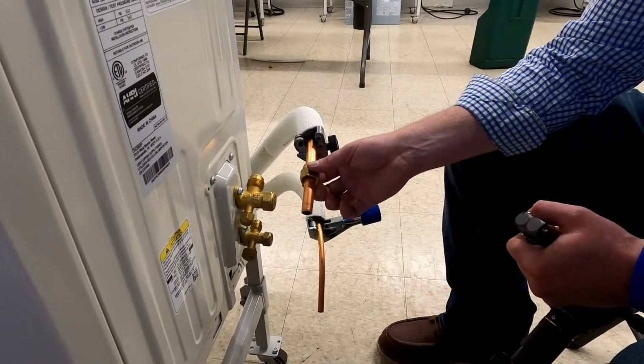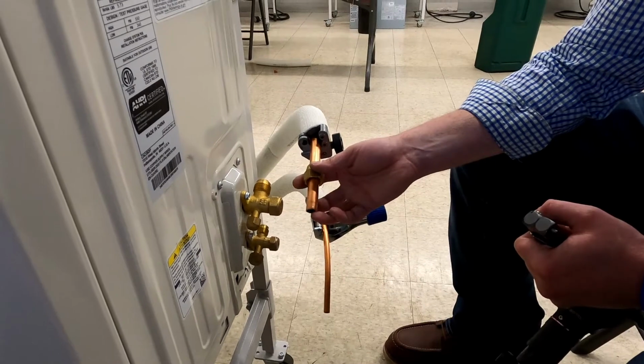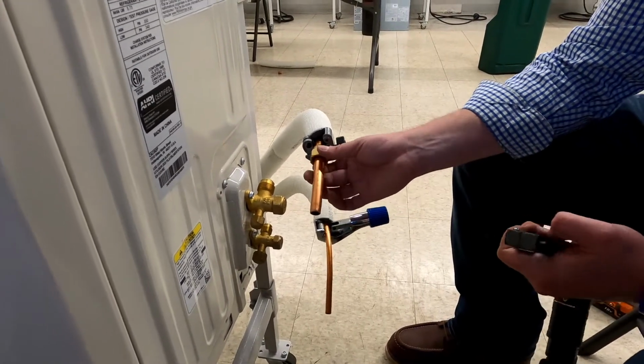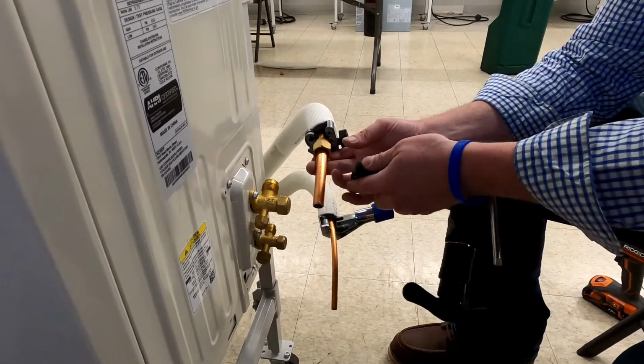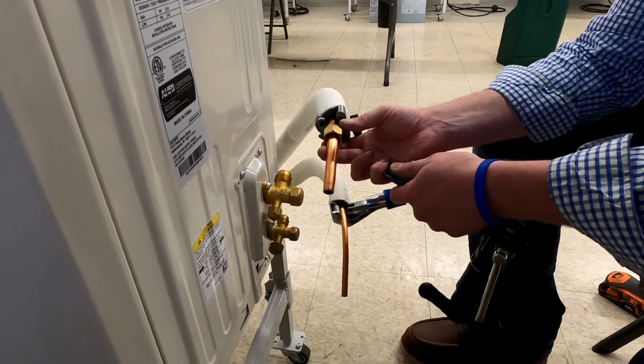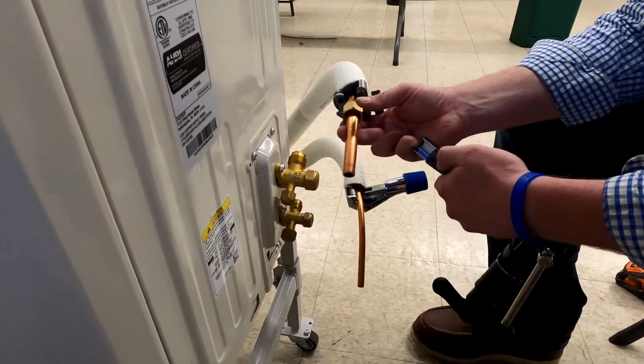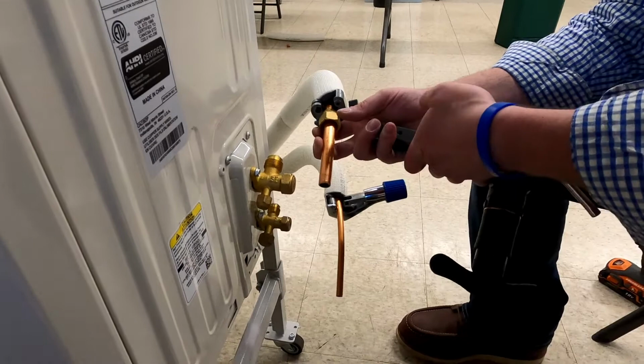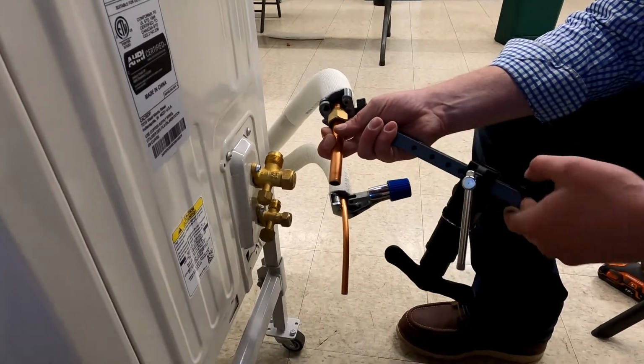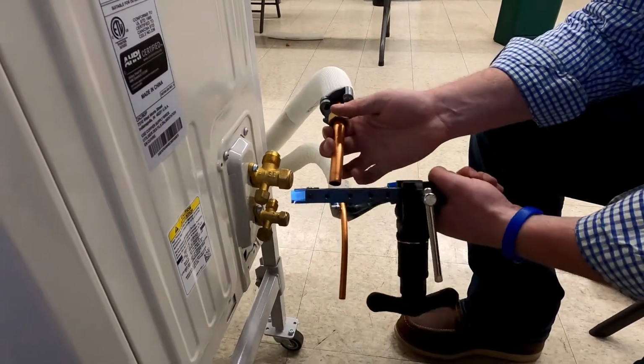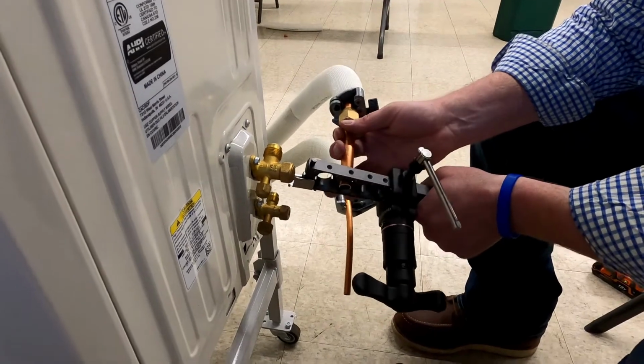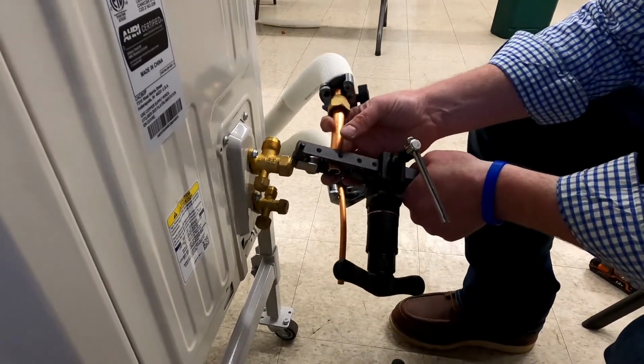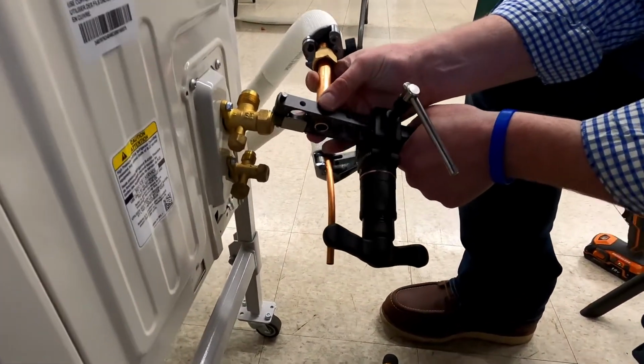All right, so now that our pipe is cut and we've cleaned out the inside after cutting it, you want to make sure that you put your flare nut on. I prefer to use the ones that are on the unit just from experience and what I've heard from other contractors. They seem to have more success with the flare nut that came with the unit as opposed to one that's on the line set.